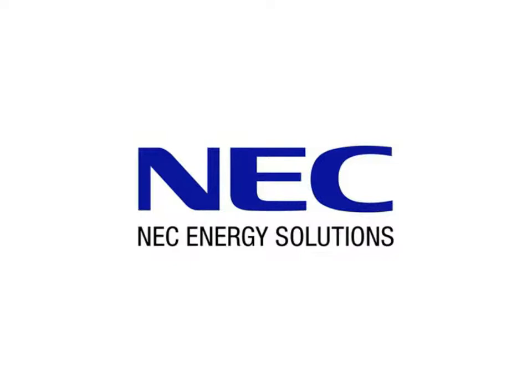That benefits factor does decrease over time. So as more fast resources get into the market, that benefits factor goes down, starting at 3 and dropping to 2 and eventually to 1. So at some point, as you're clearing these resources in the market, you stop counting energy storage as 3x, you start counting it as 2.5x, down to 2x, and eventually to 1x. In total, I would say today, the PJM frequency market is maybe in the 300 megawatt size in nameplate rating. And that takes into account the benefits factor and the fact that in PJM you need both fast and slow responding resources to ensure that the system is balanced at all times.